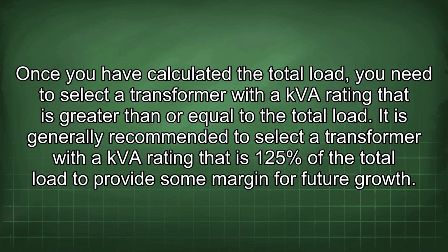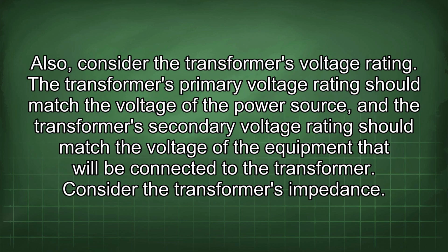entire system. Once you have calculated the total load, you need to select a transformer with a kVA rating that is greater than or equal to the total load. It is generally recommended to select a transformer with a kVA rating that is 125% of the total load to provide some margin for future growth. Also, consider the transformer's voltage rating. The transformer's primary voltage rating should match the voltage of the power source, and the transformer's secondary voltage rating should match the voltage of the equipment that will be connected to the transformer.